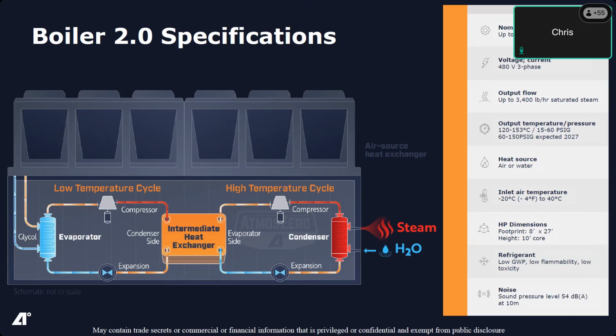These are 480 volt systems, so low voltage 3-phase power. 1 megawatt is about 3,400 pounds of steam per hour. And so we can turn that down as well, about 30%. So you can go from 100 to 70 without any efficiency penalties. You can turn down further, but that's where you start running into COP efficiency penalties.